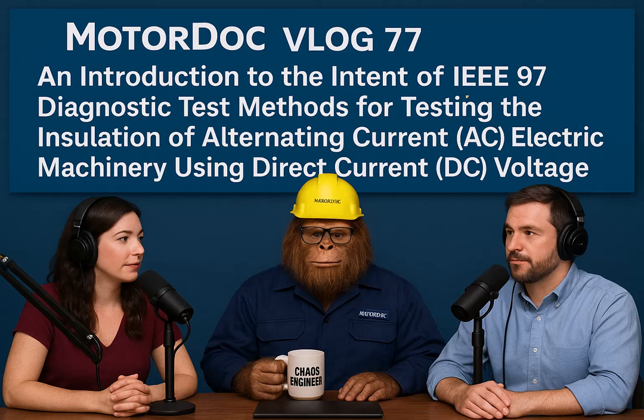So what does a low RC-depol mean? An abnormally low RC-depol value, which means you measured a high absorption current during depolarization, suggests internal problems, things like incomplete curing, thermal aging damage, maybe mechanical damage like cracking, or moisture that's been absorbed deep within the ground wall itself. Okay. And is there a nonlinearity factor for depolarization too? Yeah, like the PNLF? Yep. The depolarization nonlinearity factor, or DNLF, same idea.